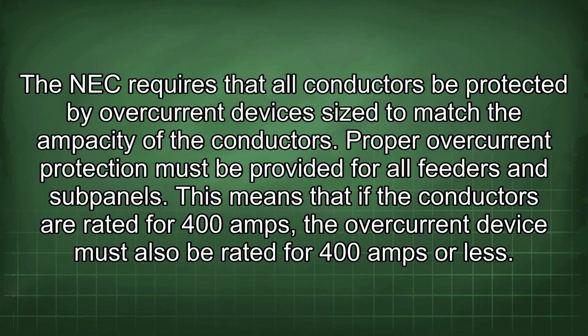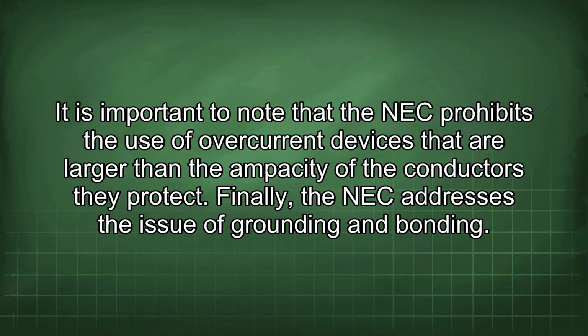This means that if the conductors are rated for 400 amps, the overcurrent device must also be rated for 400 amps or less. It is important to note that the NEC prohibits the use of overcurrent devices that are larger than the ampacity of the conductors they protect.